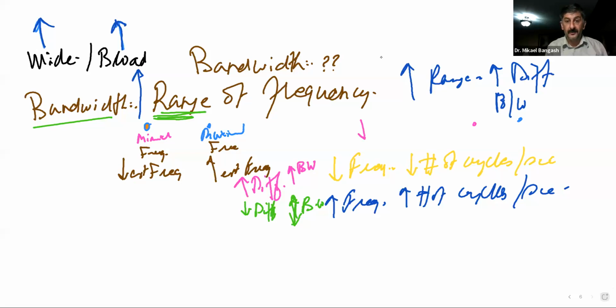Now you see your note box on page 118, where they talk about the bandwidth. Please remember, we already said that as a consequence of the backing material, or damping material, the transducer became a pulse wave transducer. So the main effect we got from adding a backing material was that we got a pulsed wave transducer, versus a continuous wave.